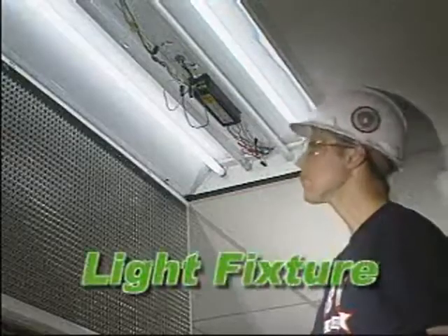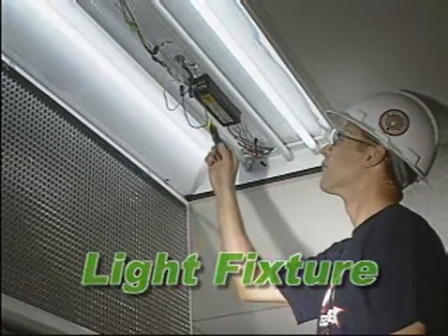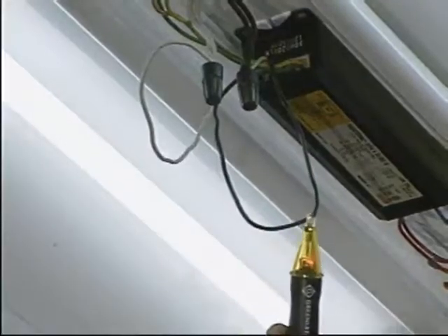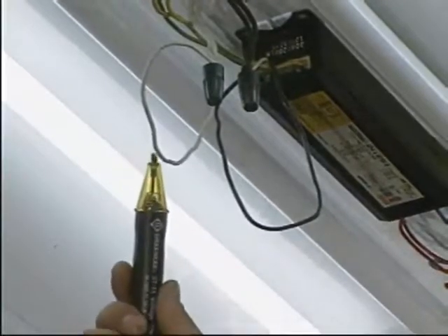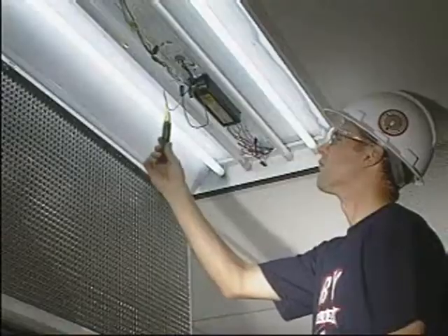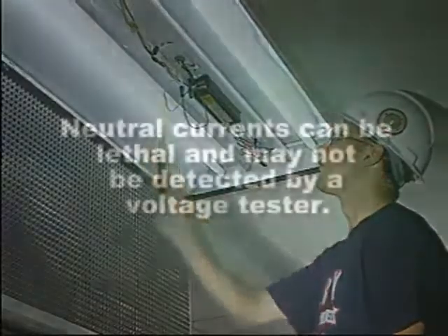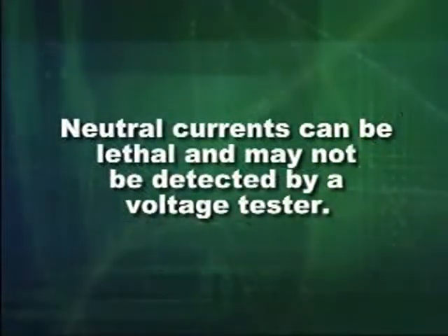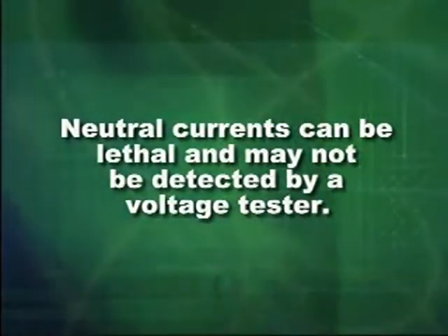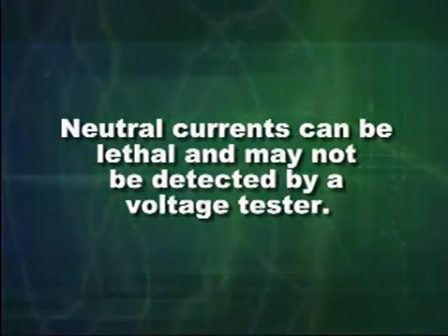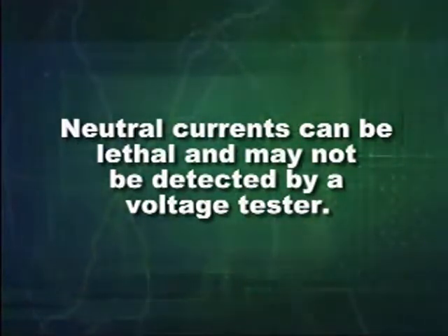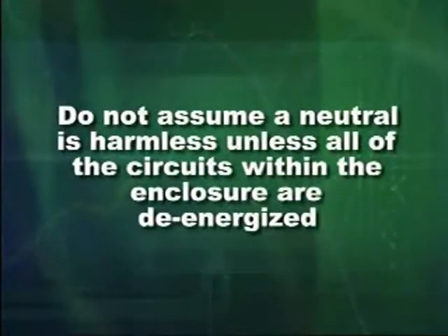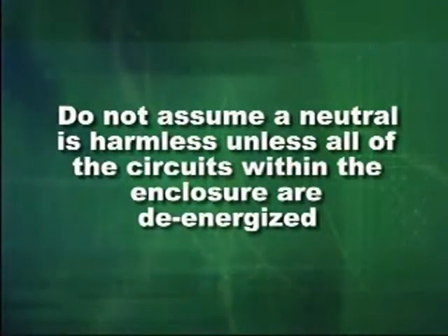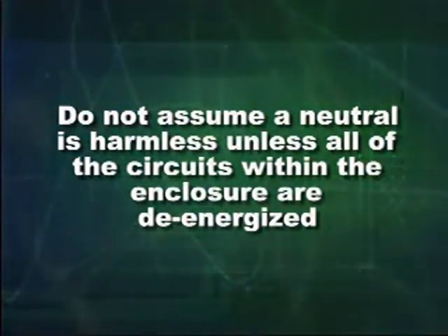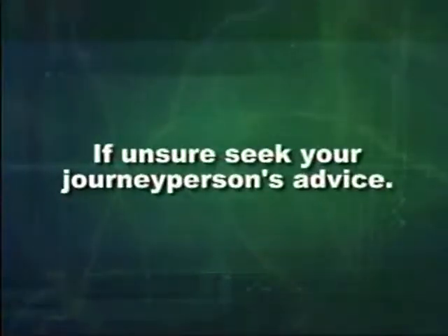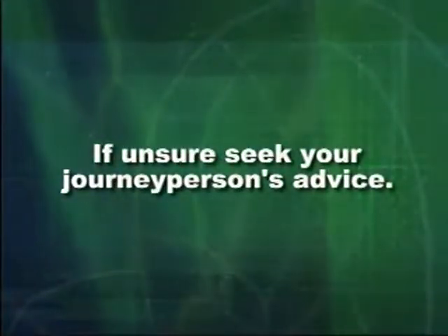To test a light fixture, slide the probe tip along the black wire feeding the ballast. If you encounter an audible or visual alarm, see your journeyperson. Also, check the white wire, the neutral. There should be no alarm indication. Because return neutral currents found on the white conductors generally do not have potential voltage above ground, a proximity tester will not normally detect their presence. We recommend that if a multi-phase system is encountered, all circuits within the enclosure being tested be de-energized before commencing work. If unsure, seek your journeyperson's advice.